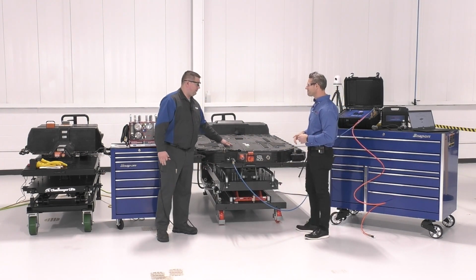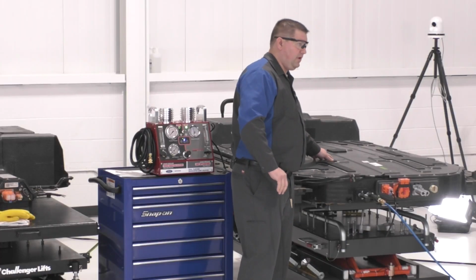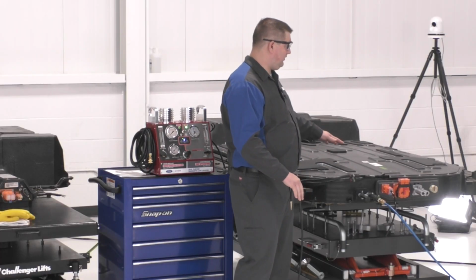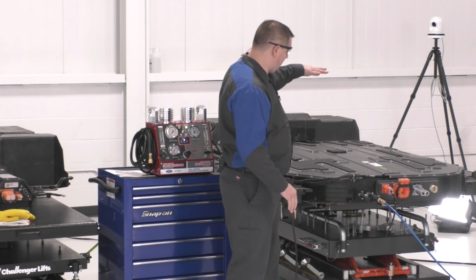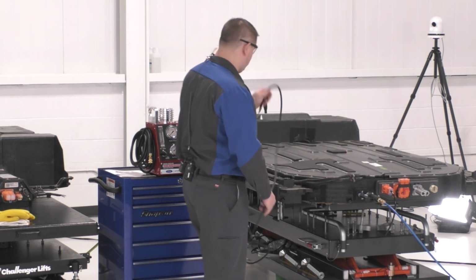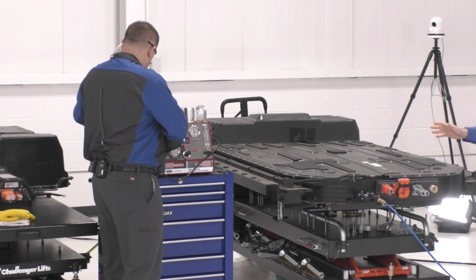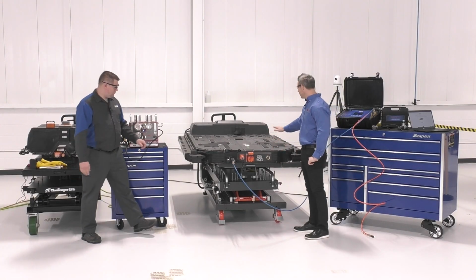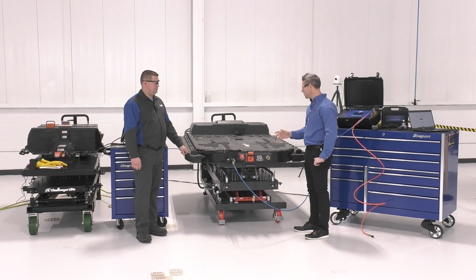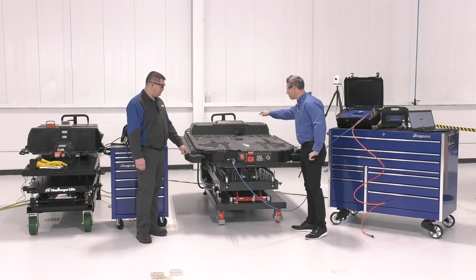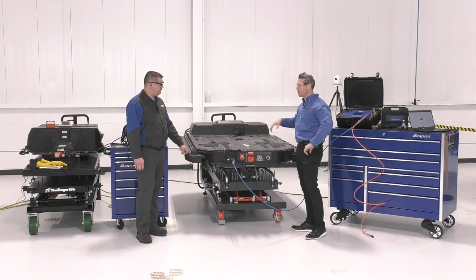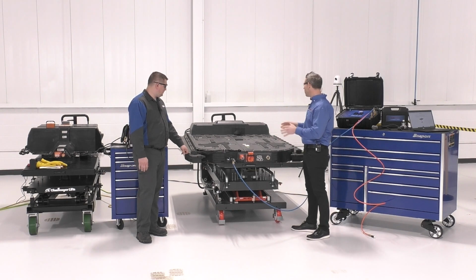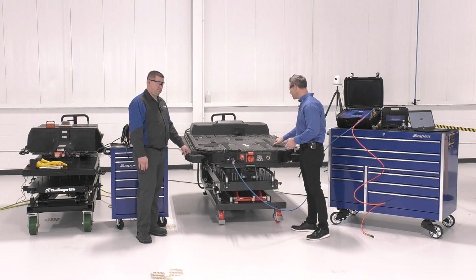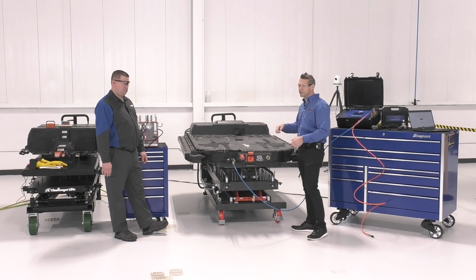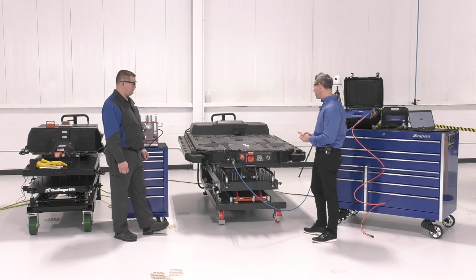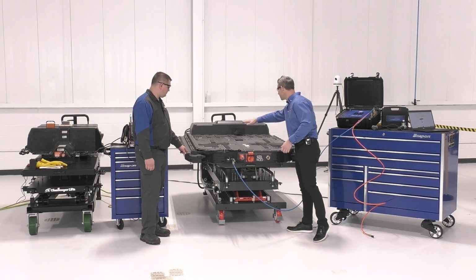One of the cool things we noticed when we started doing this test is this cover, because it's a composite cover, actually swells up a little bit like a balloon as you fill the enclosure, and then as we let the pressure out, it drops back down. This cover is really just an SMC kind of cover. All these batteries are constructed differently - some use metal covers, some bolt in the middle, and they don't expand that much. They all kind of expand a little, but this one is more of a balloon since it's a very large, single-piece cover. One advantage of that is you don't have to worry about leaks at the top of the cover.